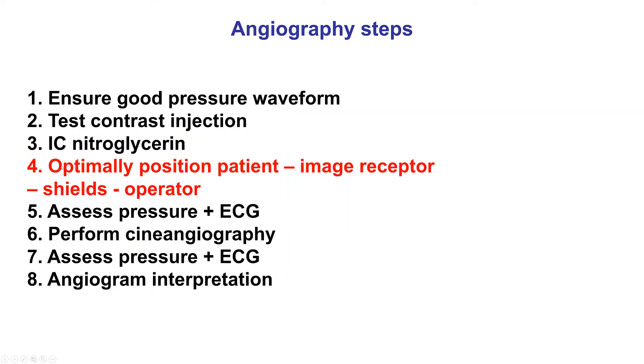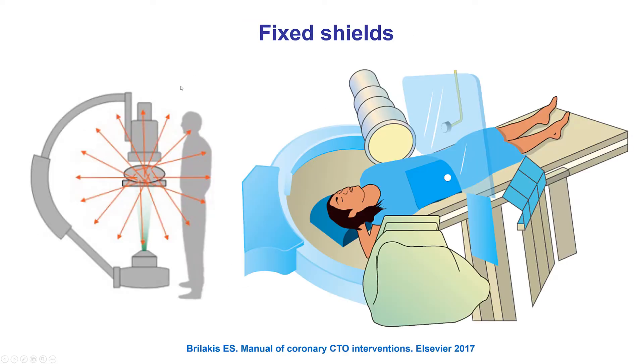Step four is to optimally position the patient, as well as the image receptor, the shields, and the operator, in order first to optimize the imaging, and second to minimize scatter radiation to the operators. The table should be as high as possible. The image receptor should be as close as possible to the patient. Shields should be placed between the patient and the operator. And the operator should be moved as far back as possible, since scatter radiation intensity is inversely proportional to the square of the distance between the scatter point and the operator.